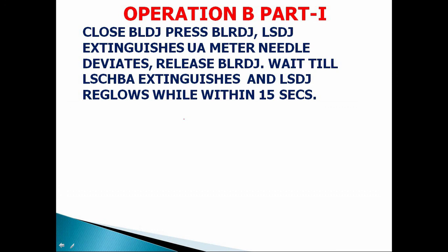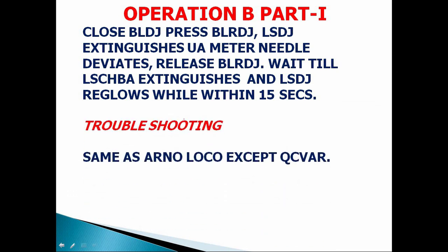Abnormal sign is close BLDJ and press BLRDJ, LSDJ extinguishes, UA meter needle deviates. Now we will release BLRDJ. Wait till LSCHBA is extinguished and LSDJ reglows while counting 15 seconds. It is almost similar to operation B part 1 of Arno. So after extinguishing of LSCHBA while counting 15 seconds, LSDJ reglows, that is DJ trips. The troubleshooting procedure is same like that of an Arno except QCVAR, that is troubleshoot for MVSL1 or QVSL1, MVSL2 or QVSL2, MPH or QPH.